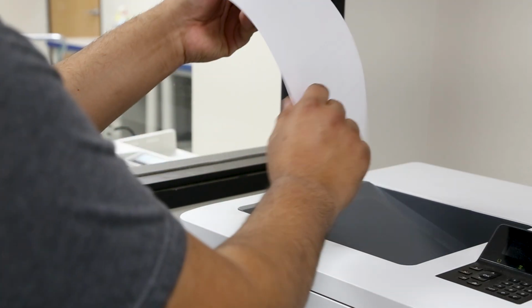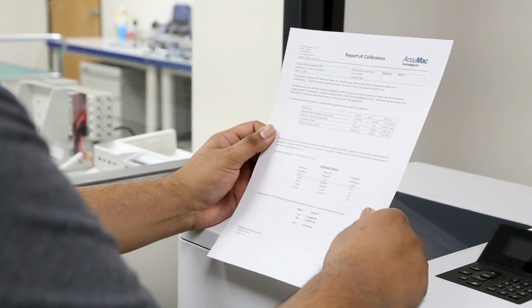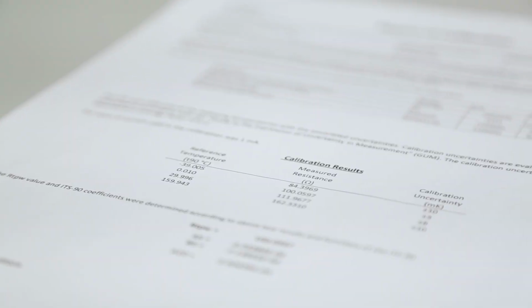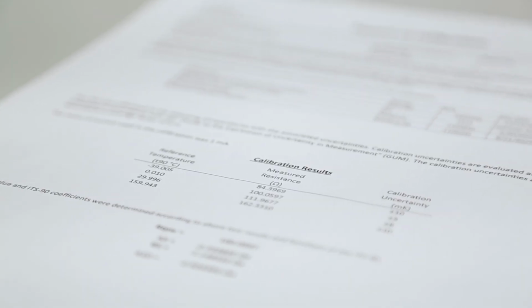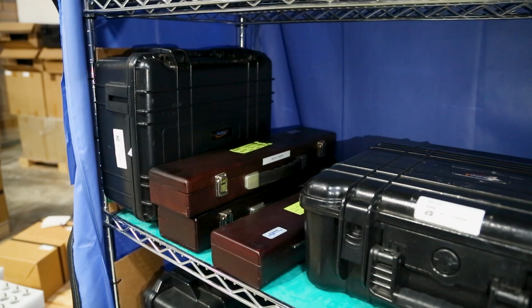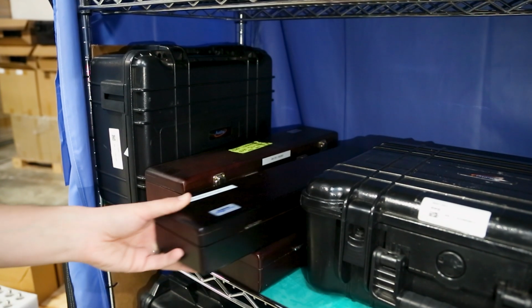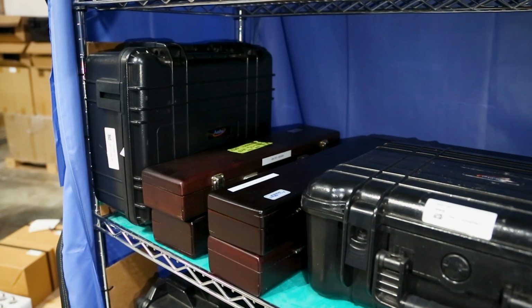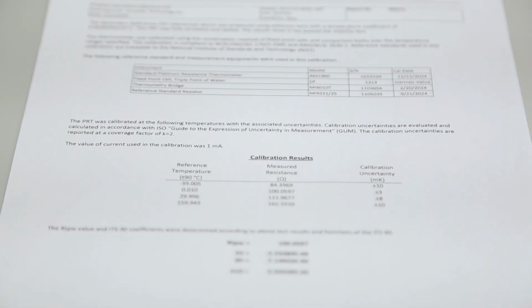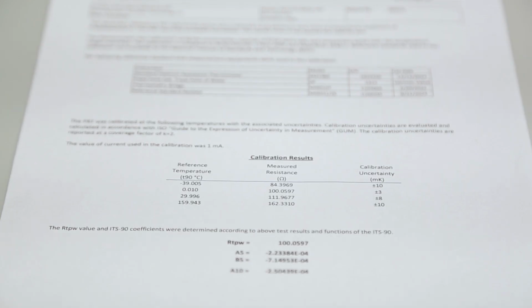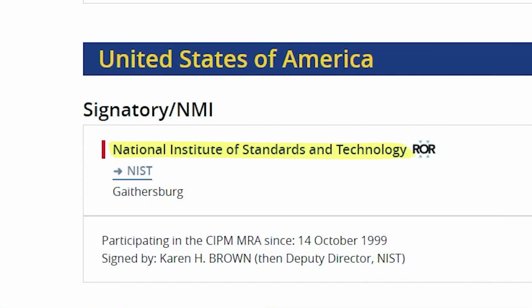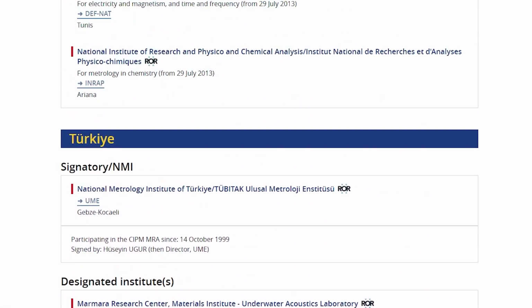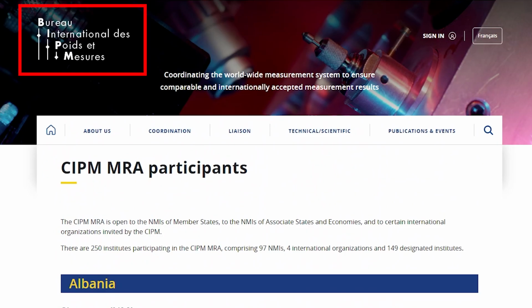In both cases, calibration reports should be generated for the completed tests, detailing the calibration process, results, and adjustments made. This allows for quality control and compliance across an organization's entire range of temperature measurement devices. These reports also establish traceability to a governing national or international body, such as NIST or other national metrology institutes recognized by the International Committee for Weights and Measures.